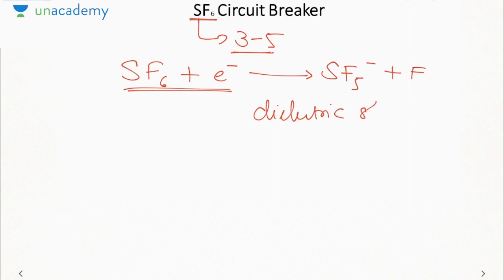Due to high electronegativity, electronegativity is the tendency to absorb electrons. So SF6 has high electronegativity, hence it absorbs the electrons and reduces the number of charge carriers in the air gap between the circuit breaker plates. Hence its dielectric strength is very high. But it is used between the voltages 1 kilovolt to 220 kV.